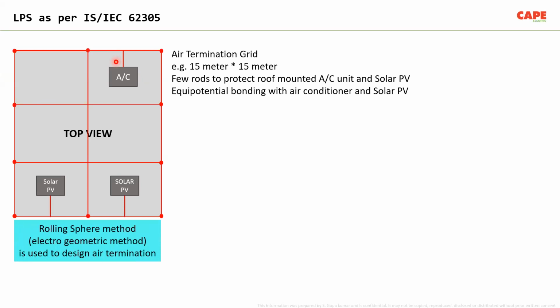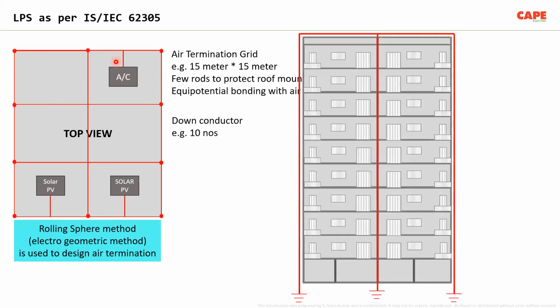Now, the second part is the down conductor. Let us say in this particular case, 10 down conductors are required. From the top to bottom, 10 down conductors are running as straight as possible. And finally, all these 10 are connected to the earth pit or earth electrode through test links. Now, the equipotential bonding between the down conductor and the MET. MET is a part of your electrical installation, the earth bus bar in the mains terminal or in the main distribution board. You are supposed to have an equipotential bonding here.